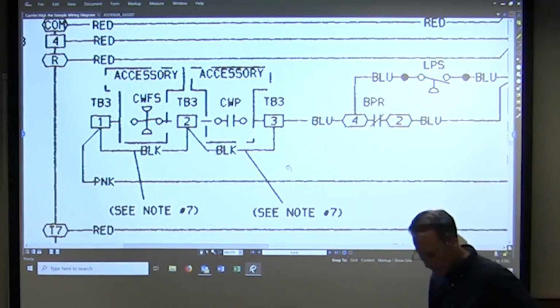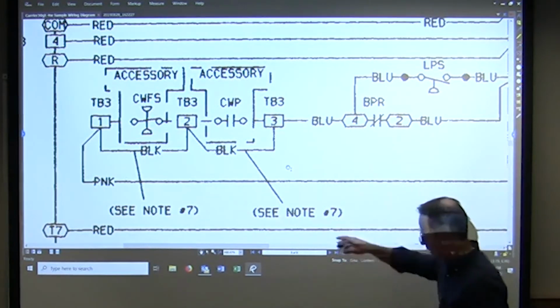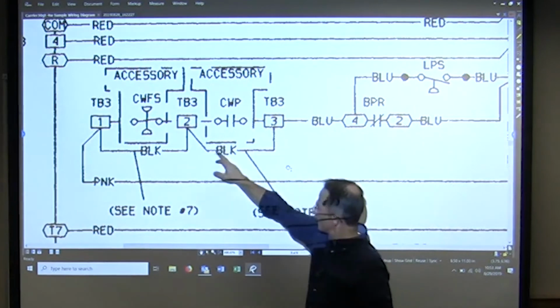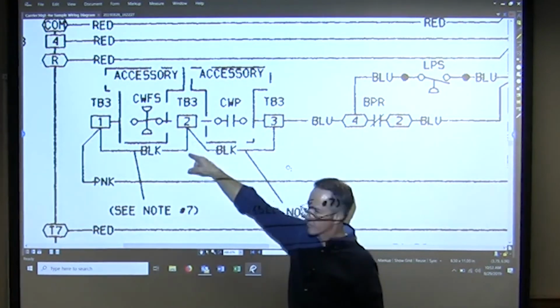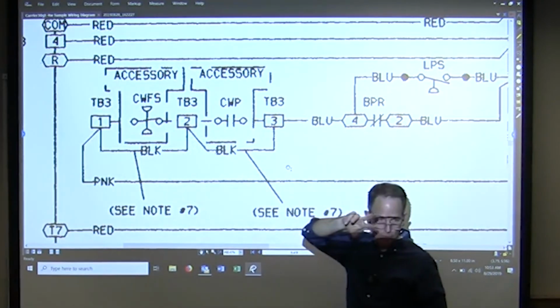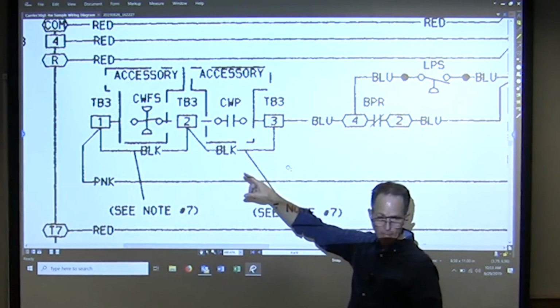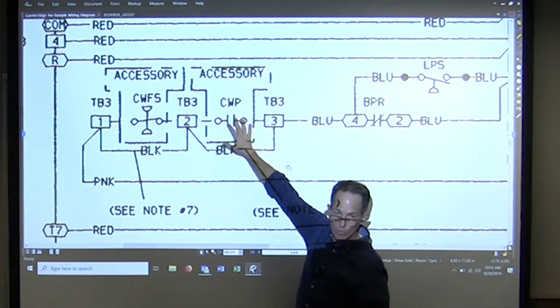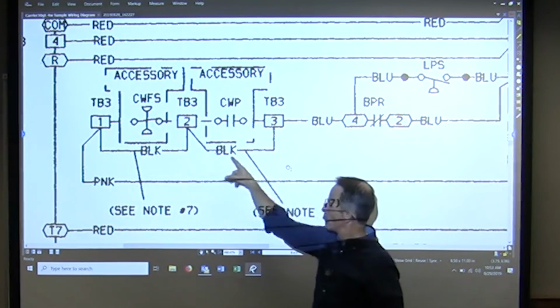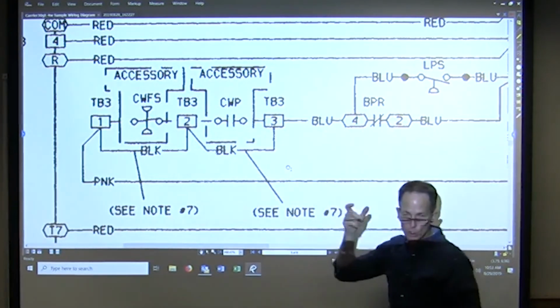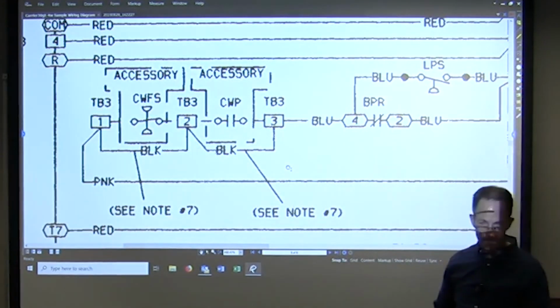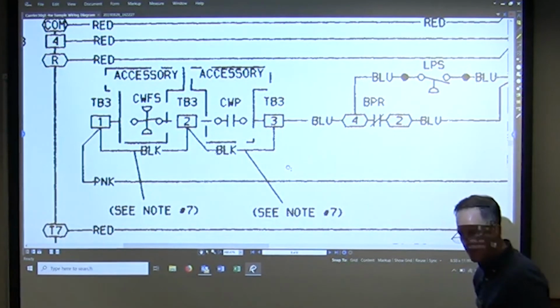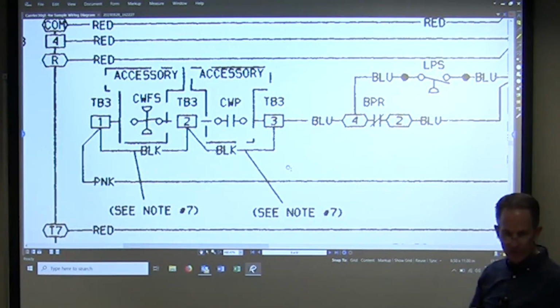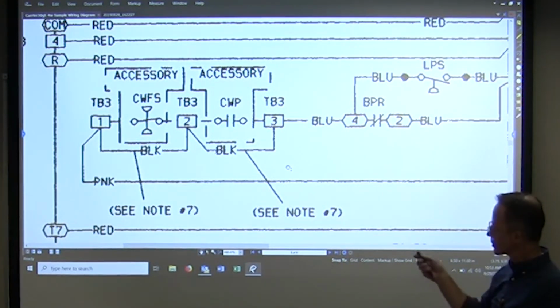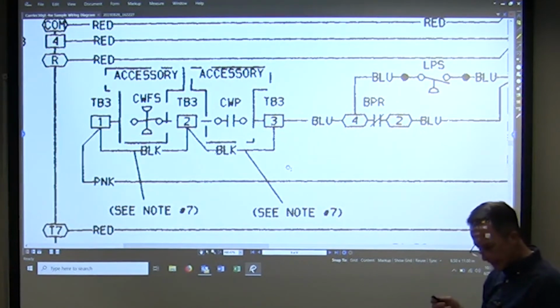Okay, it's already installed. It comes from the factory, taking the place of that. So that's this wire here, this black wire, and it's the same on 1 and 2. So our first two questions are the same kind of thing. If I have the safety interlock, I then remove the jumper wire that was installed at the factory, and that's where the safety switch goes. Right. So does that make sense to everybody? Any questions on that? Okay.